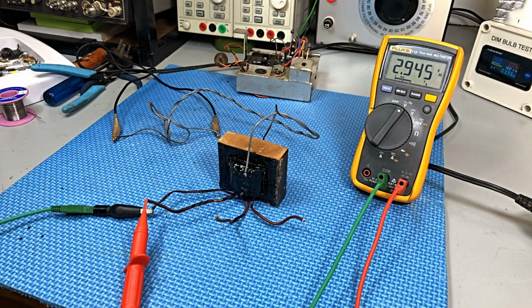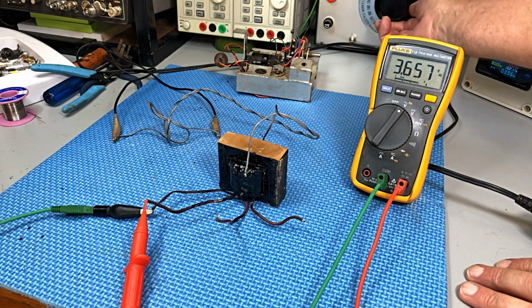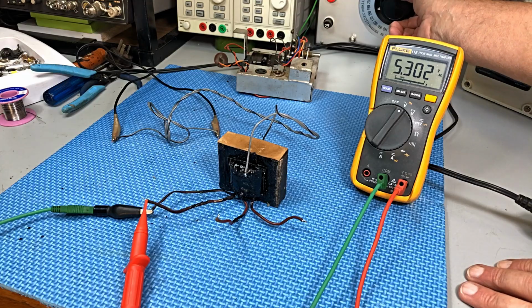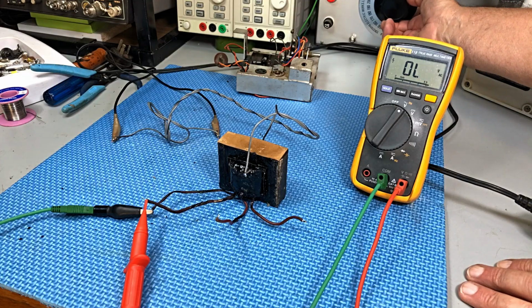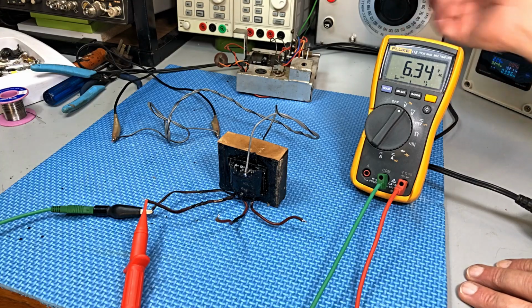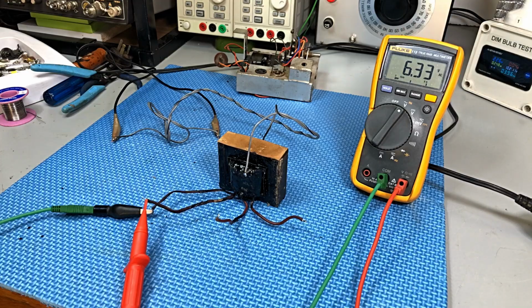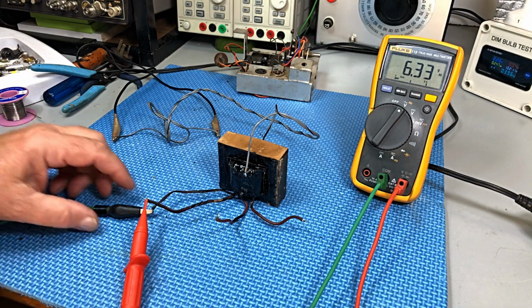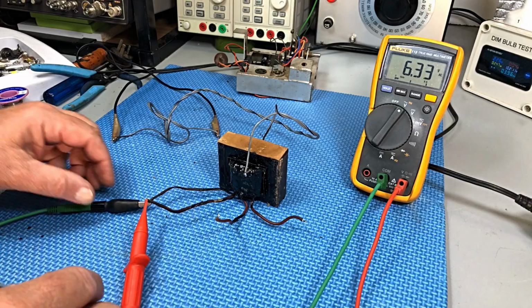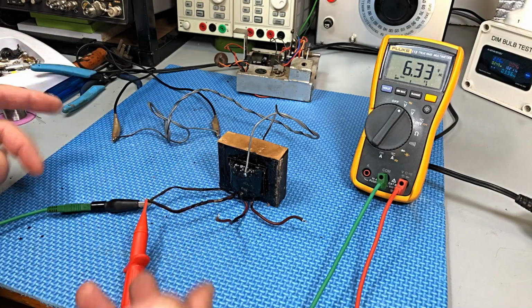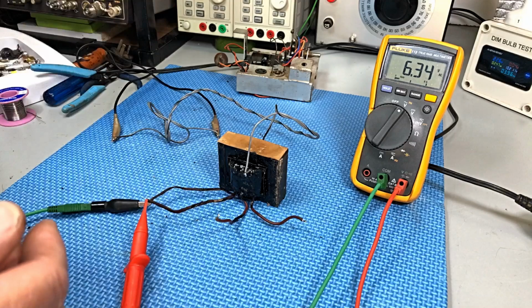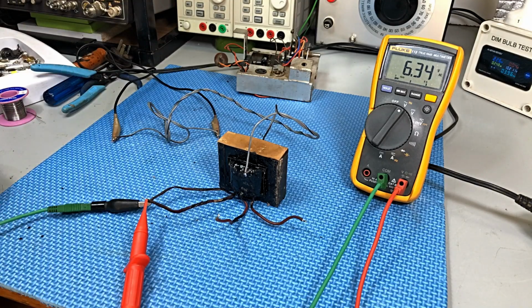So if we cruise our voltage up a bit, and if we go up to 240, we're on 230 there, we've got 6.3 volts. Okay, so I think our transformer is okay, even though it's reading high on the primary. Well, there's 6.3 at 230 volts, which is correct.